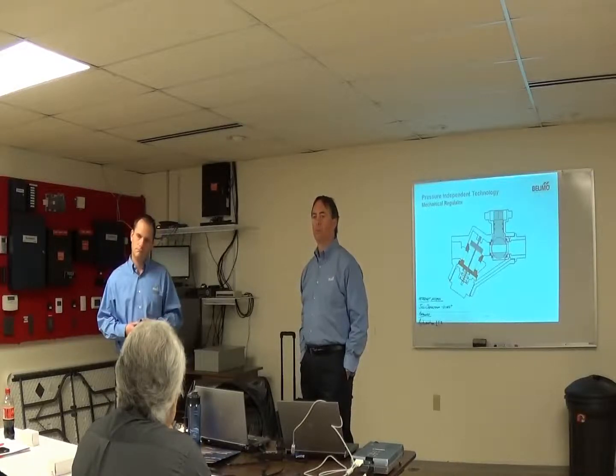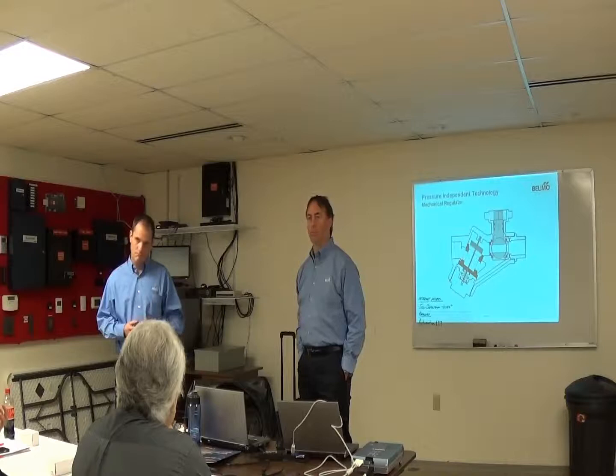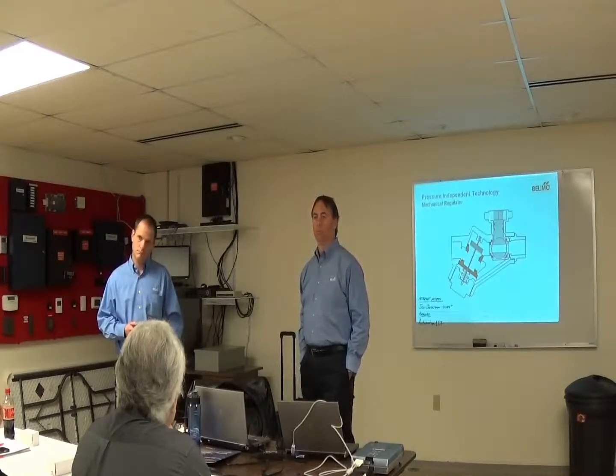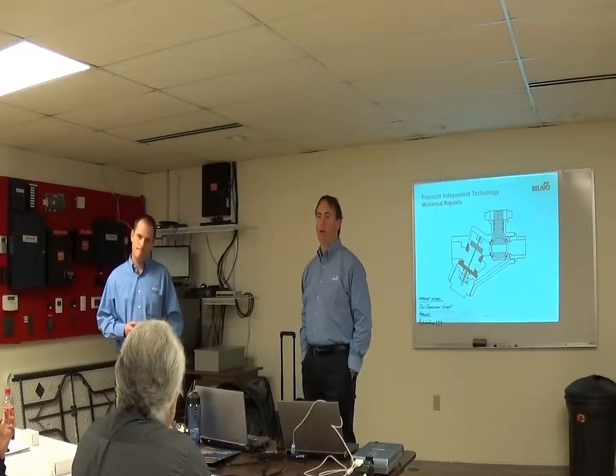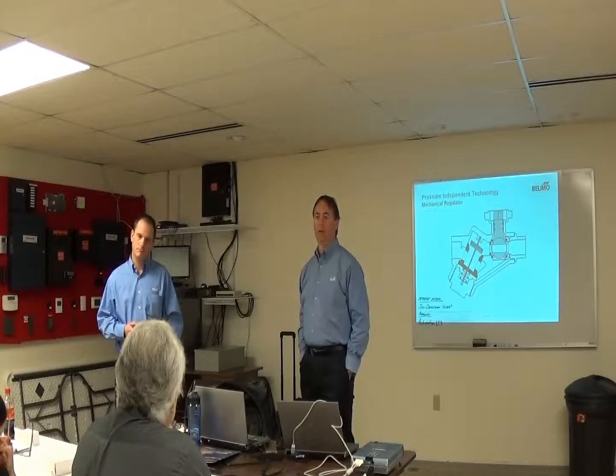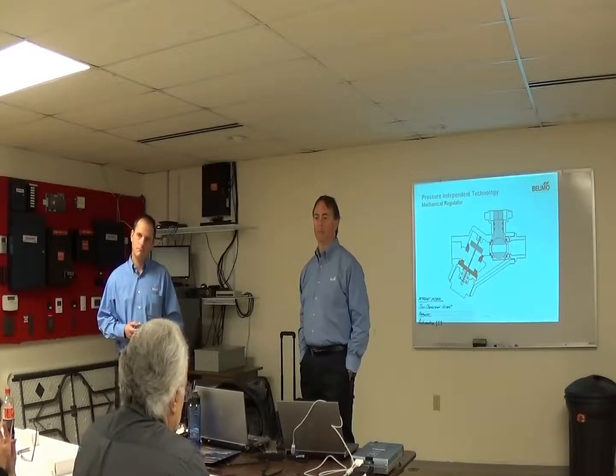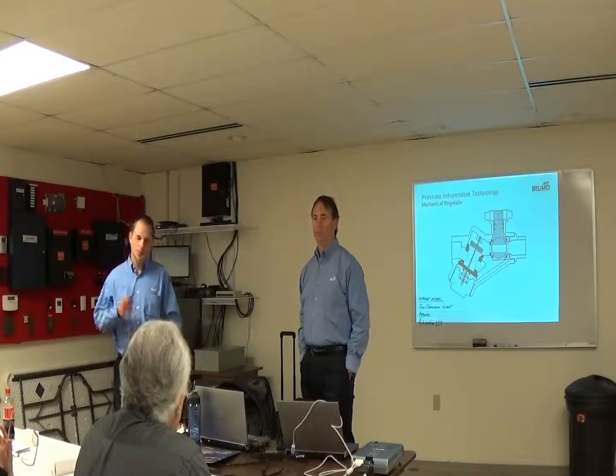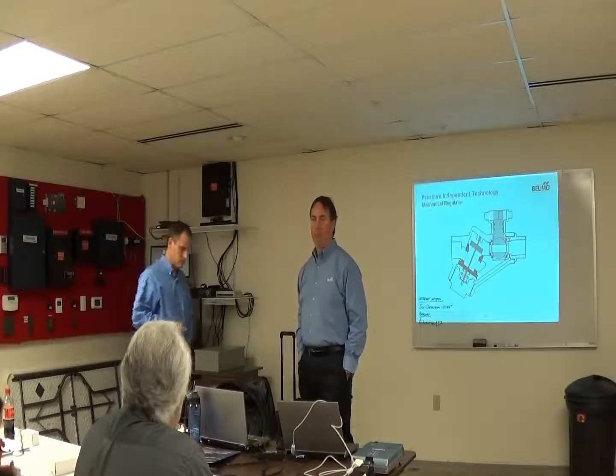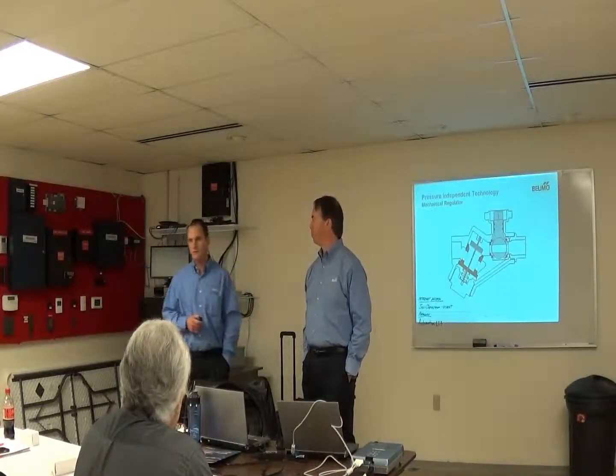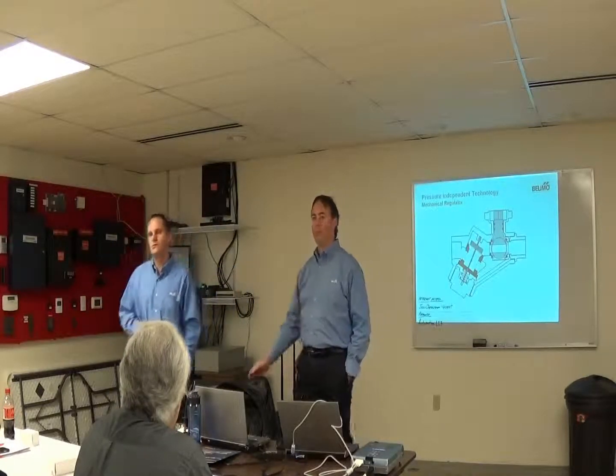And just like you said with the 5 to 50, I think if I'm right, all we do is tell our balancer, just go to each air handling unit, look at that differential pressure. If it's within that range, it's fine. Just check it. Make sure it's in that range. They don't do anything. If it's not within that range, then I'm not sure what they can do. But we just have them check it. If it's in this range, then it's controlling to the flow that we've specified. So that's what we tell them. They just check it. Yeah, right.